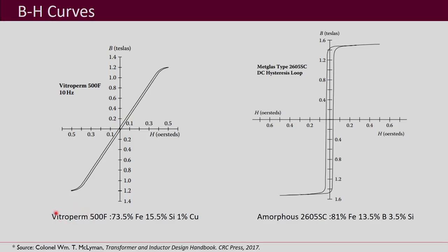This material Vitroperm 500F has the composition 73.5% iron, 15.5% silicon, and 1% copper. The BH curve obtained is shown here — the H-axis is expressed in Oersteds, which is the CGS unit of magnetic field intensity H. For amorphous 2605SC, another magnetic material, the BH curve looks very different — the residual flux is much higher although the coercivity is lesser. Whereas for Vitroperm, both residual flux and coercivity are very small.